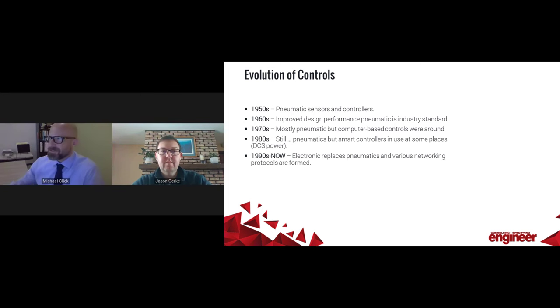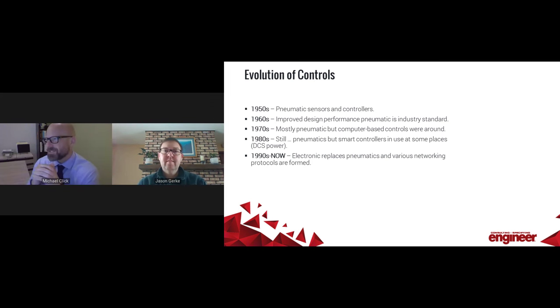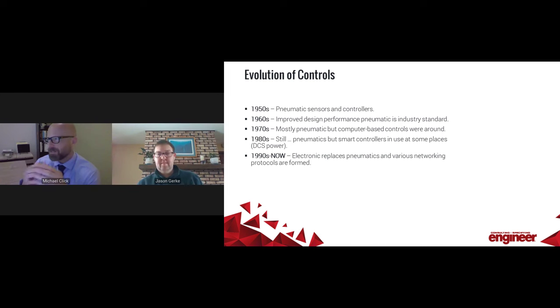In order to assess controls for design, we thought it would be important to quickly understand the origin and background of how far we've come in the controls industry. Pneumatics were one of the first original control systems. Pneumatic control systems operate by compressing air, which is then dried and sent down a piping called main lines. At the most basic level, the pressurized air from the main line will move through a sensing device like a thermostat. That thermostat would then allow a certain amount of pressure out of its branch lines to control the operation. This air would act as a control signal to a device like an actuator, regulating the amount of main line air entering the actuator.